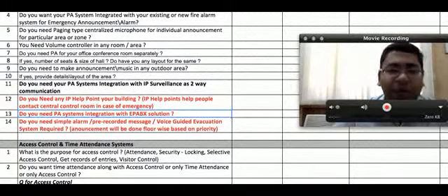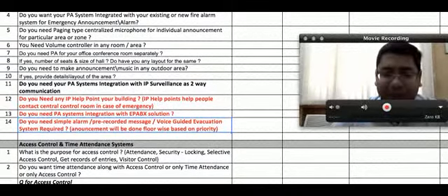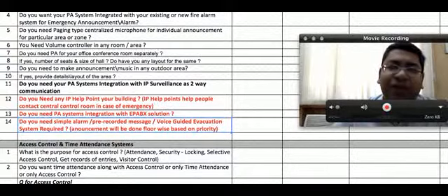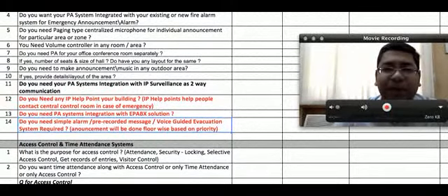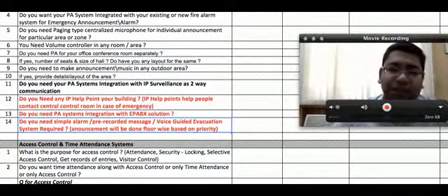The PA system can also be integrated with the EPBX system, whereby by dialing an extension number you can make announcements. Similarly, even the evacuation system, in case of an emergency or fire, can be voice guided. So if there is a fire in an 8-floor building, then the evacuation will happen floor by floor. Instead of making an announcement to all 8 floors at the same time, which may lead to a stampede, it is better to make the announcement one floor at a time.